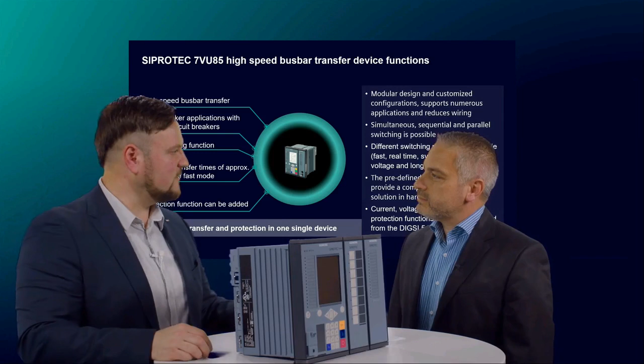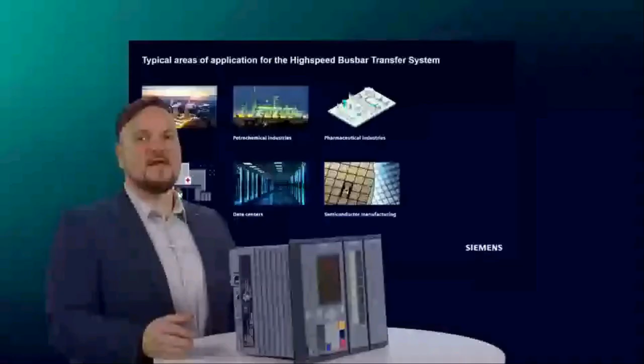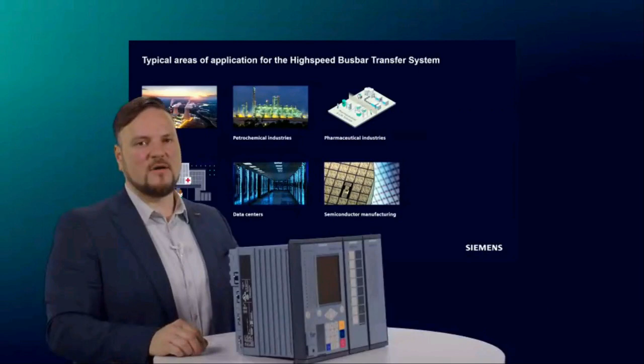Okay, now what about the typical areas of application? Where is the HSBT used? Here we see the typical areas of application for HSBT functionality. A high-speed busbar transfer device is typically required where a continuous power supply is needed for inductive motor operation in critical parts of a production process. This is ensured by connecting an alternative incoming feeder in standby mode. This is often the case in petrochemical, pharmaceutical, data center, hospital, and semiconductor industries with continuous processes, as well as in power generation plants.